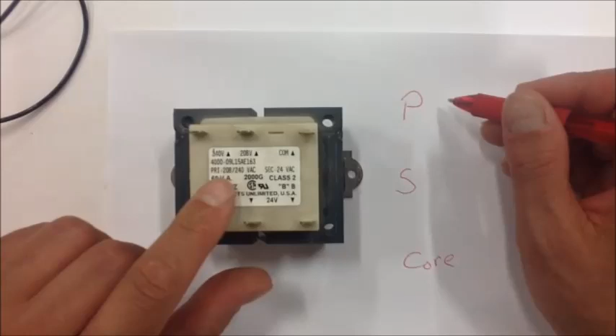and this transformer has some versatility in that it's a multi-tap transformer. You can see we've got a couple of voltage options here on the primary. We've got this terminal over here. This is called the common terminal, and it's in common with either this terminal or this terminal right here. So if we're going to use 240 volt for the primary, we would use this terminal and that terminal. And if we were using 208 volt for the primary, we'd use that terminal and that terminal.